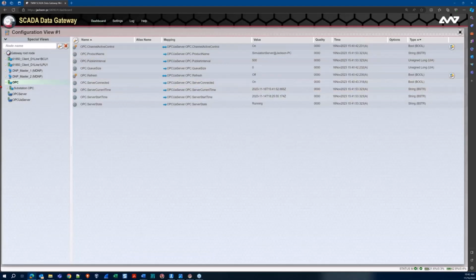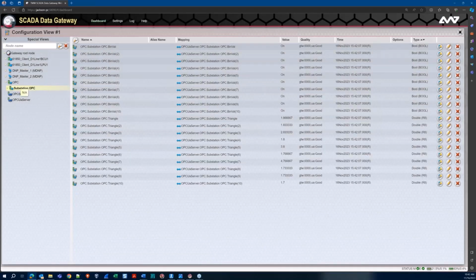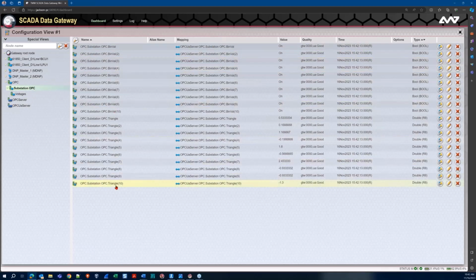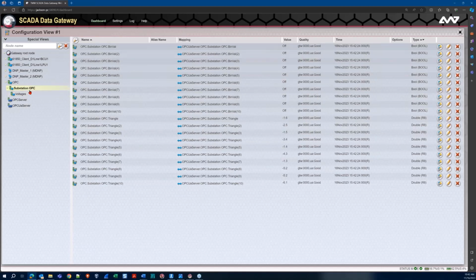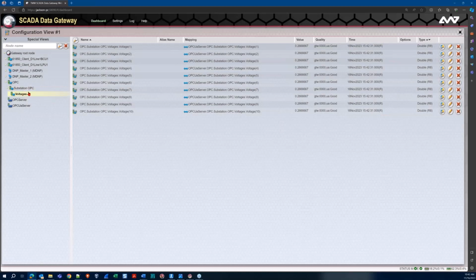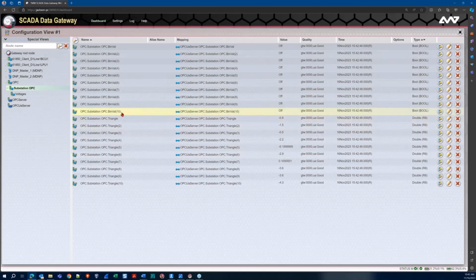I can now close out of this, and we'll see that I've added a folder called Substation OPC underneath my OPC client. If I click on that folder, I can see the different points available at that root level within Substation OPC. As I mentioned, I had created another object, in some ways like a folder, within that Substation OPC folder called voltages. I see that appear as a child of Substation OPC, and if I click on it, I can see the 10 different voltages inside of that particular object. Again, I call them voltages, but they're really just floating point numbers that could represent any data. Of course we have floating points, binaries, strings, and so on - common OPC UA data types.